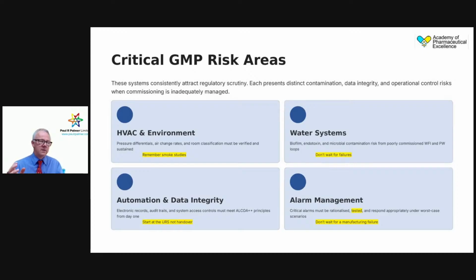Alarms is an interesting one. You can always falsify an alarm by applying something to the sensor. People don't want to, I don't know why. And then you need to set it up fully to actually send out those 3 parallel alarms that you expected in your URS. Just because it's difficult for them to test doesn't mean they shouldn't do it. And if it then needs to be done at factory acceptance and then later in the actual facility, don't mind - do the job 3 times, as long as it means it works.